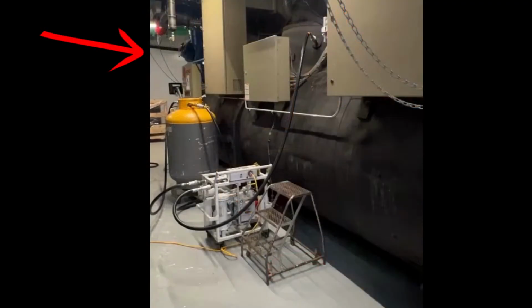So this is a Trane CVH. We've got a 1,000-pound cylinder here, and we're doing a recovery. This would be a RefTech recovery unit. Up here is your suction elbow with vapor going back in, and down here at the bottom is a liquid charging port that we're pulling from. This is an example of a push-pull recovery setup, and it's my recommended way of doing any of these. This is a low pressure chiller, but it would be the exact same setup with a high pressure chiller. There are some minor variances because of low versus high pressure and how we purge and clear the lines, but at a high level, this is the basic setup.